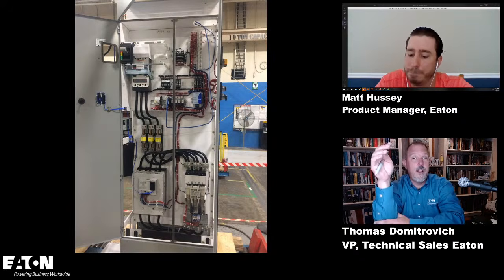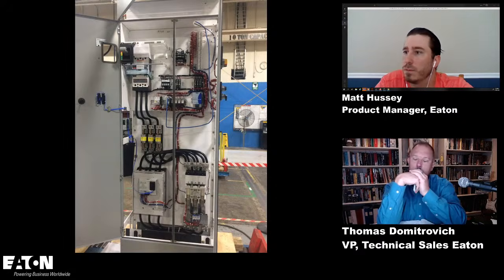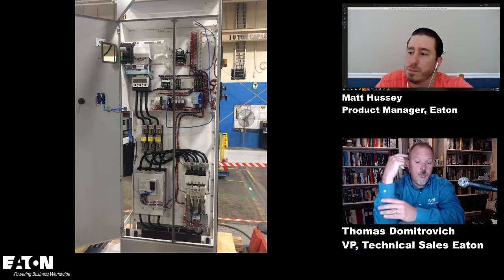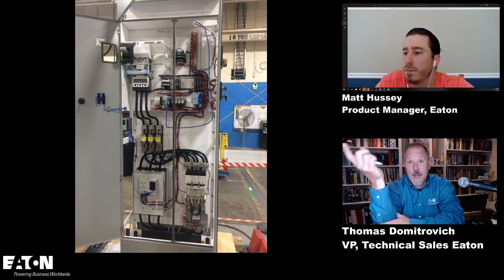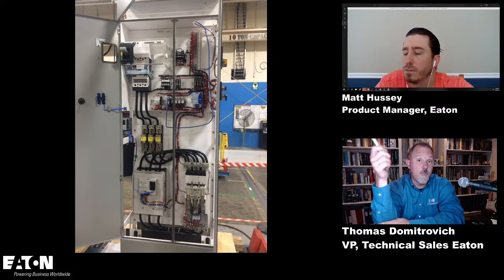Okay, and that brings up a good point. When you throw in a variable frequency drive or some of those types of things that isolate from inrush current and from short circuit contribution, when you put it in bypass mode, it bypasses all of that insulating or isolating type of equipment. So when you're doing your short circuit studies, you've got to make sure you include that motor contribution because you have those bypass switches in.